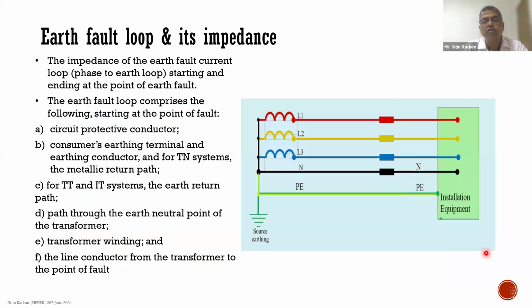So what is our fault loop? Let us understand that. Whenever there is a fault, for example, this is a point at which the fault has happened, and this will be the flow of current through the PE conductor to the star point, goes back through the L1 winding of the transformer and back to the fault point. So this is how the fault loop is available in case of faults. And the impedance value of this fault loop has to be according to the values that were specified in the chart earlier given in the slides, which is also available in the code.